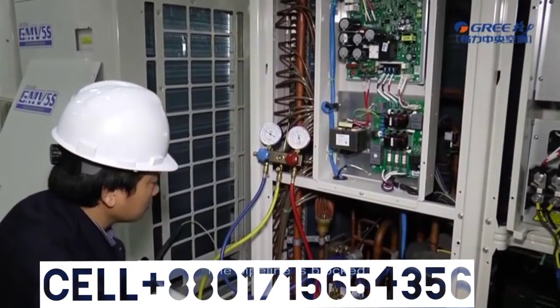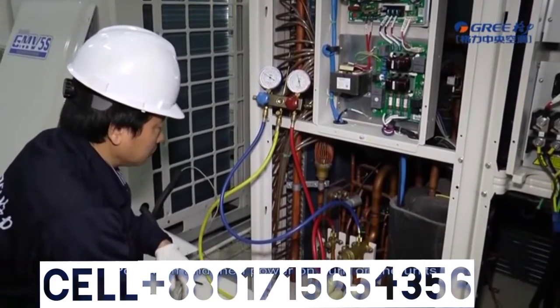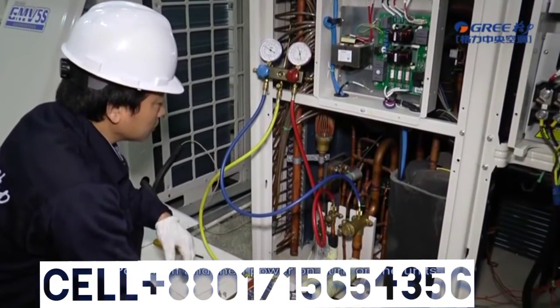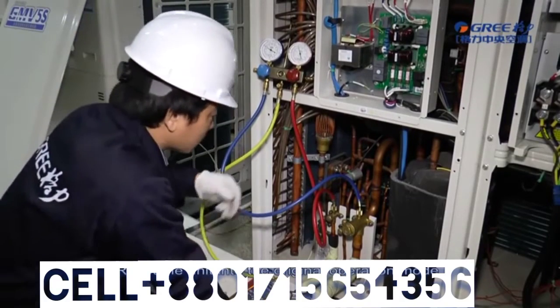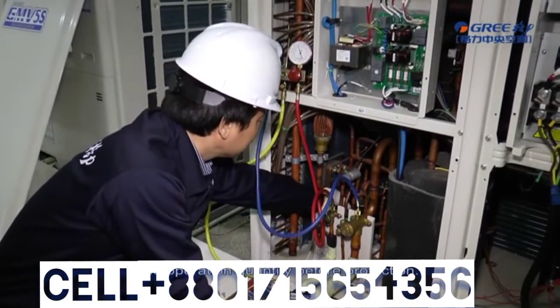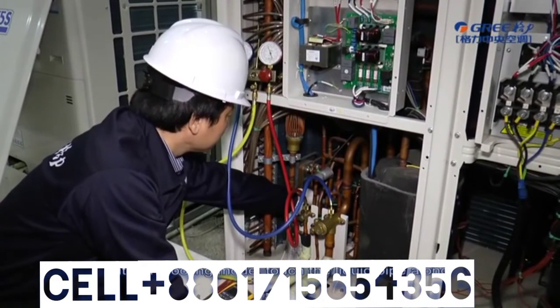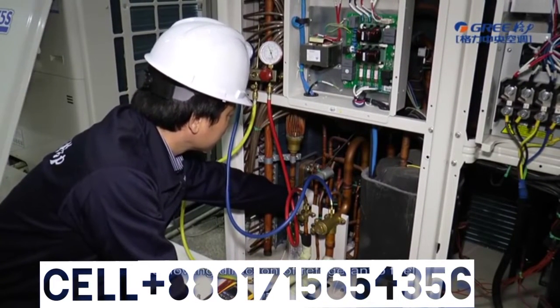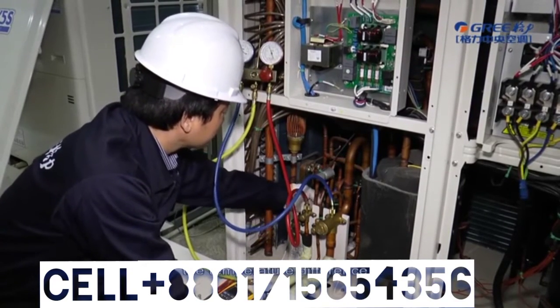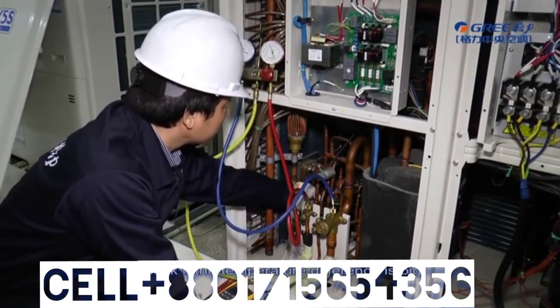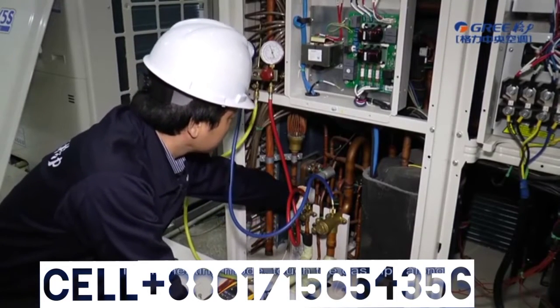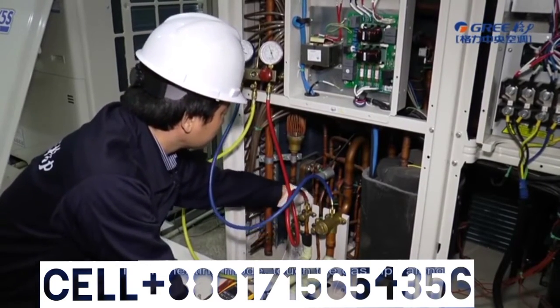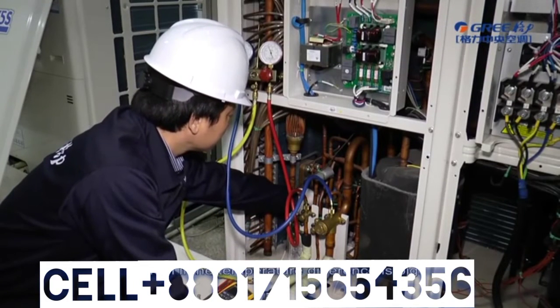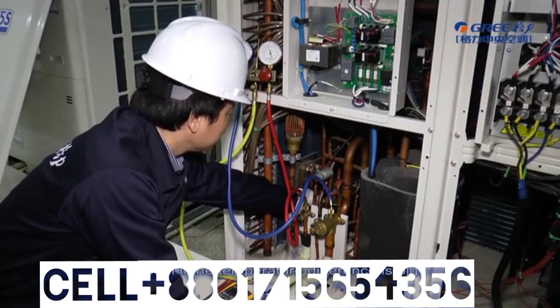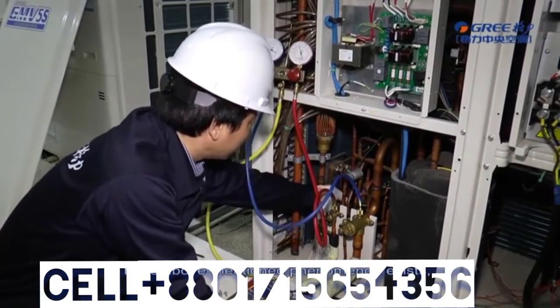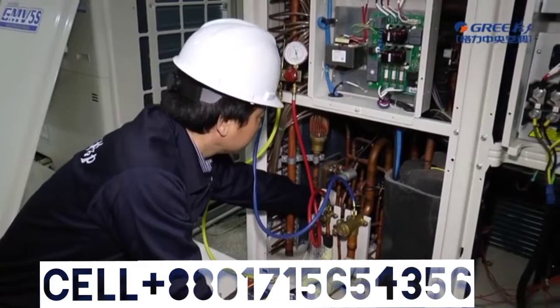6. The pipeline is blocked. Power off and then power on. Turn on the units. Reset the unit into the original operation mode and operation quantity before protection. If it is in cooling mode, touch the liquid pipe along the flowing direction of the refrigerant to feel the temperature difference. Check if the difference is big or part of the pipe is frosting. If it is in heating mode, touch the gas pipe along the flowing direction of the refrigerant to feel if the temperature difference is big. If the above-mentioned phenomenon exists, it means the pipeline is blocked.